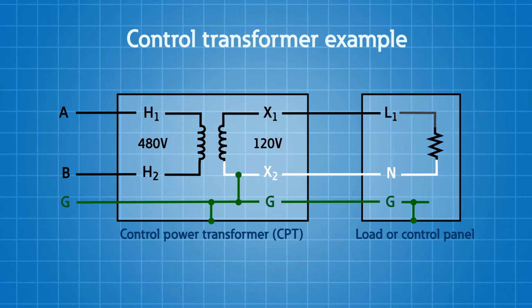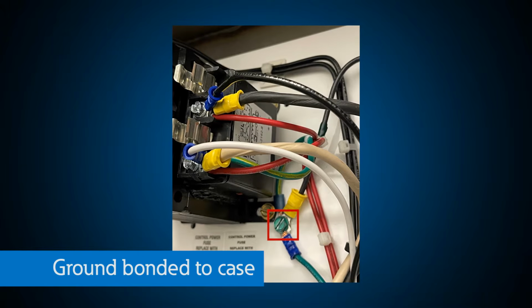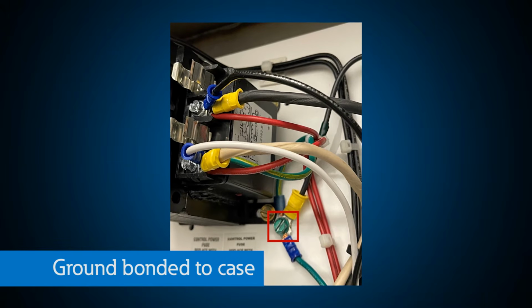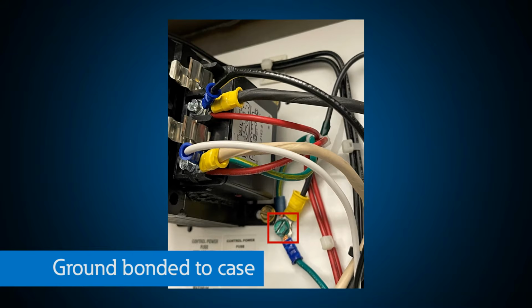This ground would also be bonded to the transformer case to ensure that the case and all metal parts remain at a constant potential for reference to the known ground conductor. I've seen many instances where this ground connection was not done to supposedly make it better for power quality reasons, but yet it almost always made it worse without the ground connection, and electrical equipment was damaged.